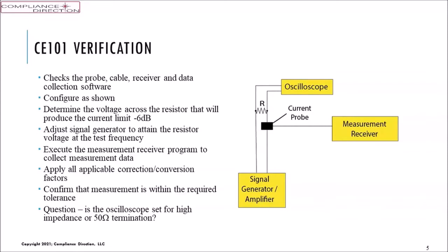Now, that resistor, what do we do here? We select a resistor that will allow us, with our generator amplifier, to produce enough voltage so the current will flow in the loop from the generator through the resistor and back. And so typically a fairly low value resistor, 20-25 ohms, is not uncommon here, so we can produce the current without having to drive such a high voltage. And we calibrate the details of getting the resistor value. Execute the software, apply the correction factors, confirm the measurements and tolerance.